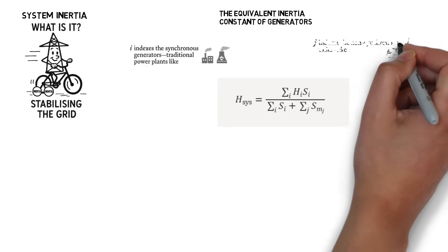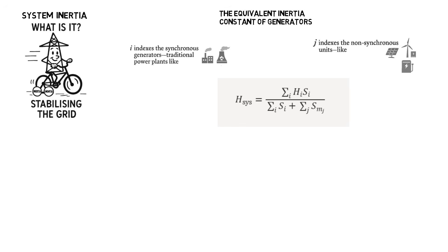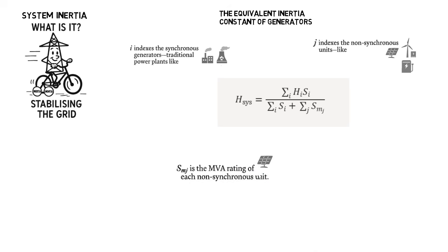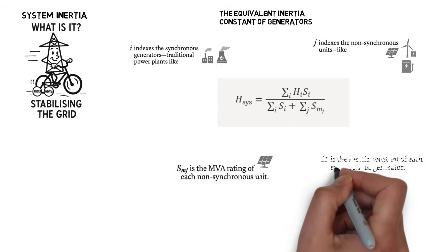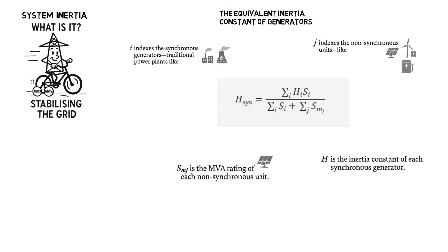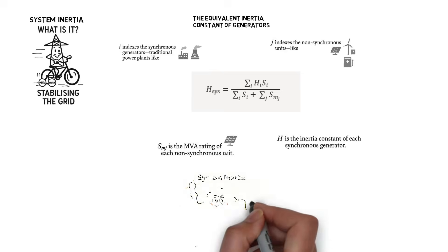J indexes the non-synchronous units, like wind turbines, solar PV, and battery inverters. S_mj is the MVA rating of each non-synchronous unit. H is the inertia constant of each synchronous generator. In practice, we sum up the inertia contributions from all the synchronous generators. Renewables? They're usually left out, because they don't provide inertia in the traditional sense.